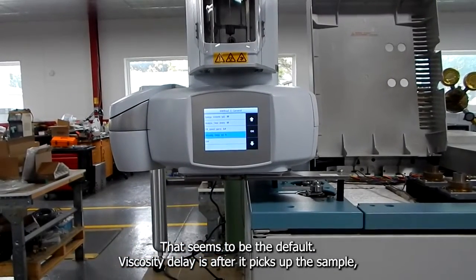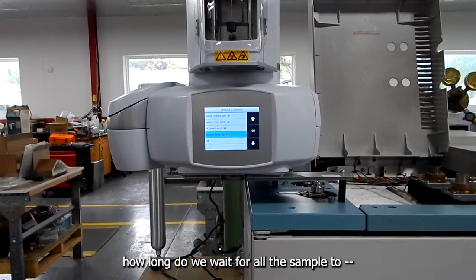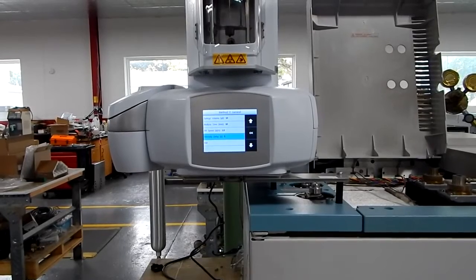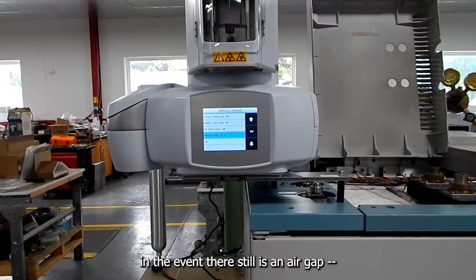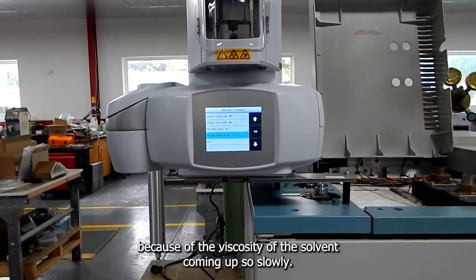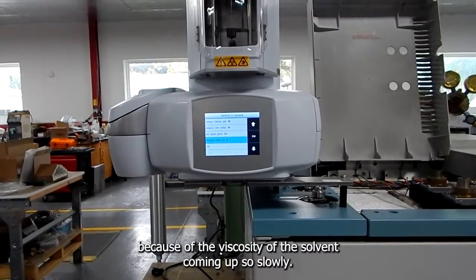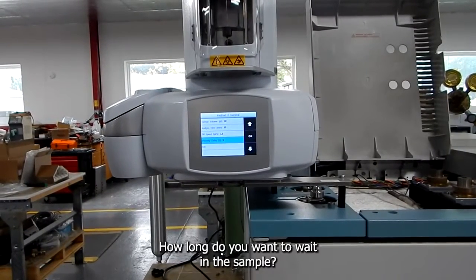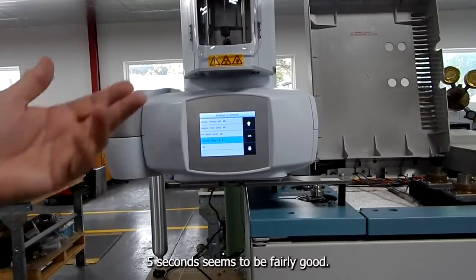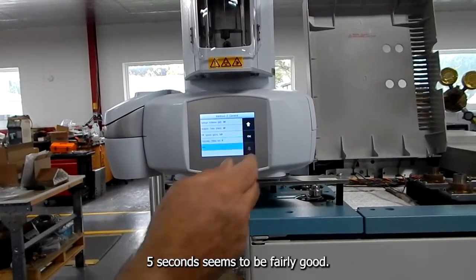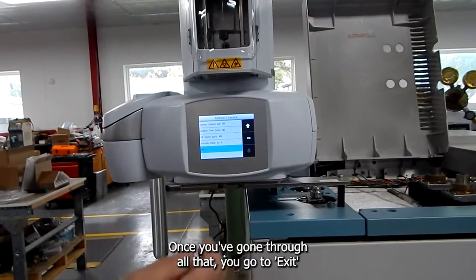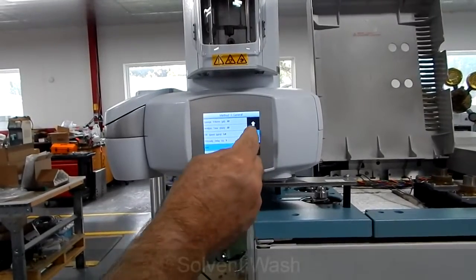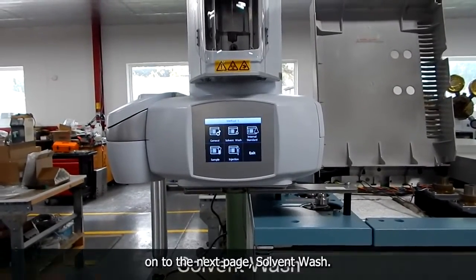Viscosity delay is after it picks up its sample, how long do we wait for all the sample to come up, in the event there still is an air gap, because of the viscosity, the solvent's coming up so slowly. How long do you want it to wait in the sample? 5 seconds seems to be fairly good.